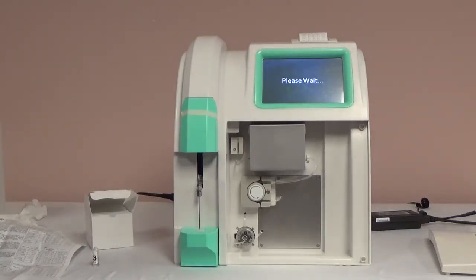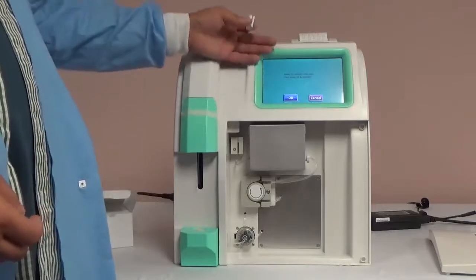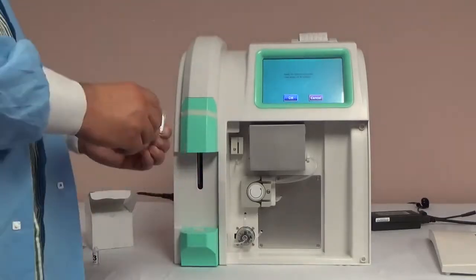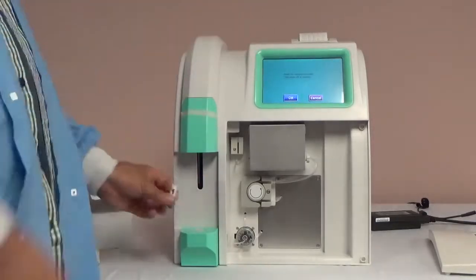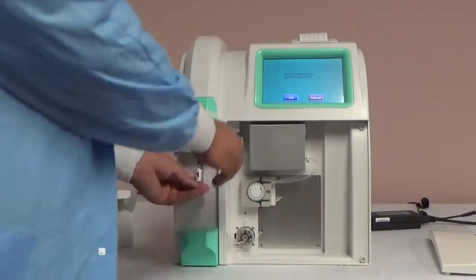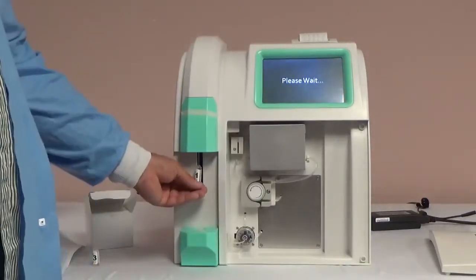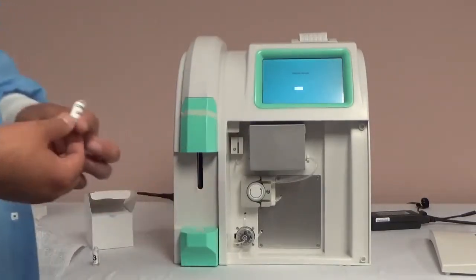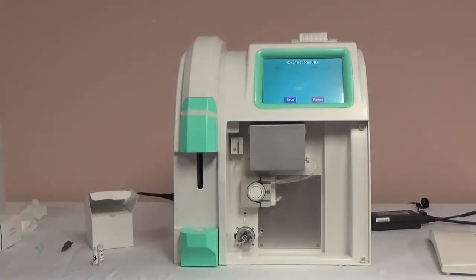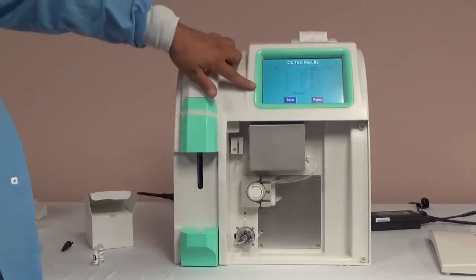When prompted, add the QC solution to the probe. Make sure you are using the solution for the specific level you selected to test. Press OK. The analyzer will display the results on the screen as well as print the result through the internal printer. You can review on the printout whether the level passed. You will complete the same steps for QC test level 1, 2, and 3.